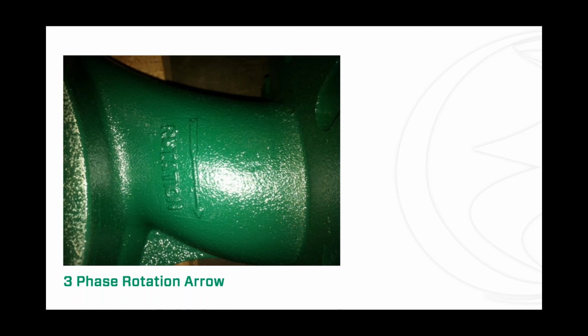The preferred way is to check rotation before putting the pump down in the pit. But if that didn't get done, here's a quick tip: you can check this without pulling the pump by shutting off the power. Three-phase pumps have three power leads going to the pump - if you switch any two of those three leads, the pump will change rotation. So flip-flop two of them and try it, using your amp probe to check. Run the pump each way and check amp draw - whichever way yields the lowest amp draw is generally correct.